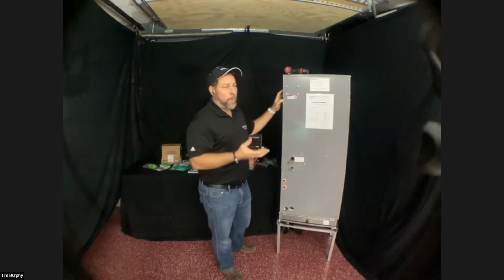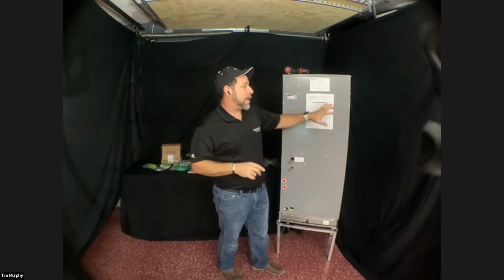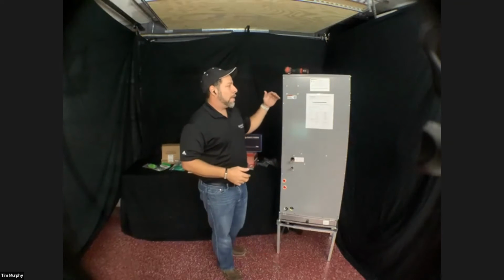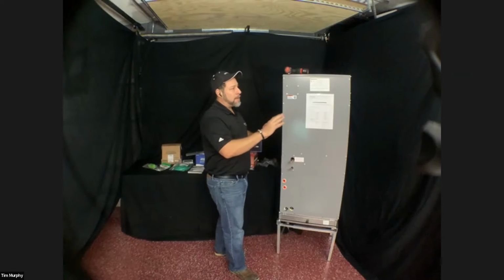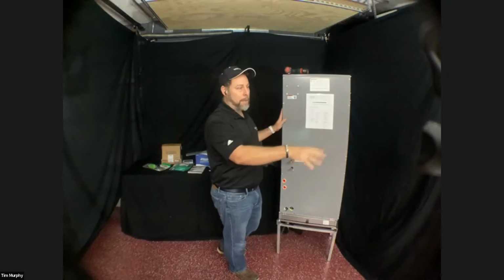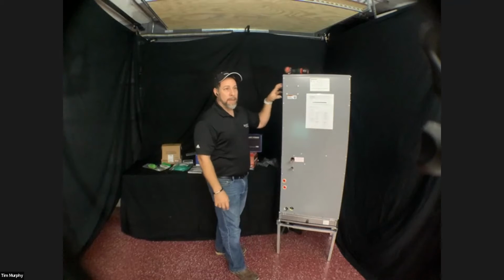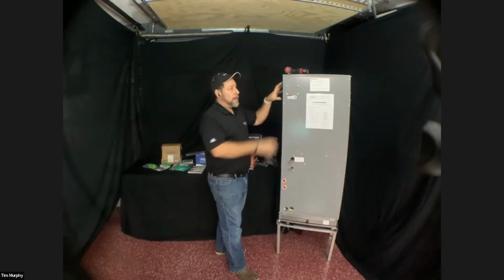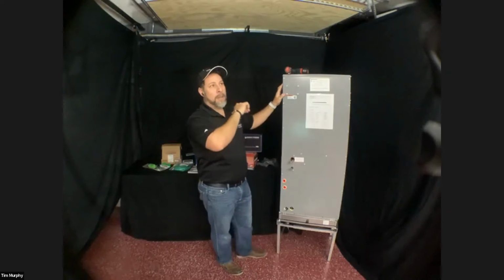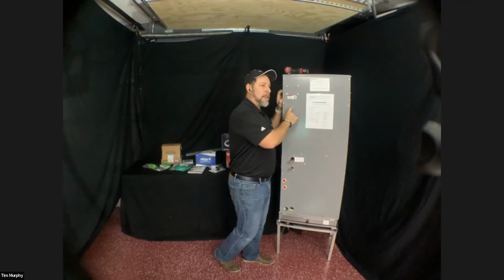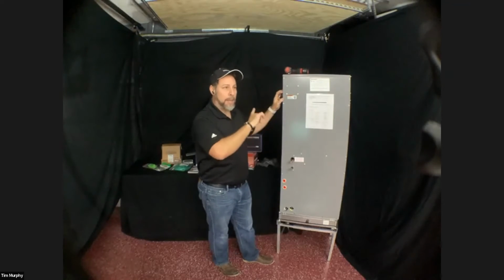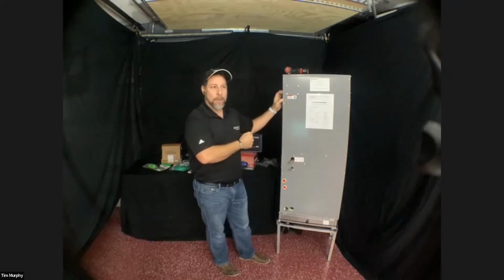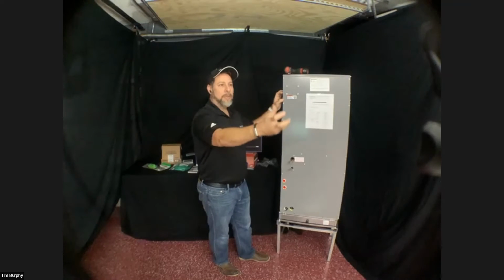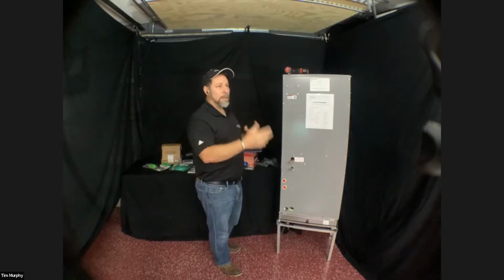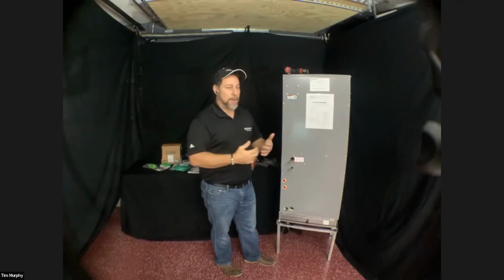Where you're going to run into issues is if you have multiple circuits, maybe this would be more commercial, they're supposed to share the same voltage. That being said, let's say you have 208 at your condenser, and you're powered from another circuit, maybe it's not on the same bus bar, and you have 208 normally. Maybe on this bus bar there's a walk-in cooler, or another big package unit, and when that unit comes on, it's going to pull voltage. You're going to drop in voltage. Why that's important is because this is going to communicate directly with the condenser. It's constant communication. It doesn't only communicate when you use the remote. It's constantly communicating the sensors back to the outdoor sensors, and using those in order to cool the home, open up the EEV, and speed up or slow down the compressor.